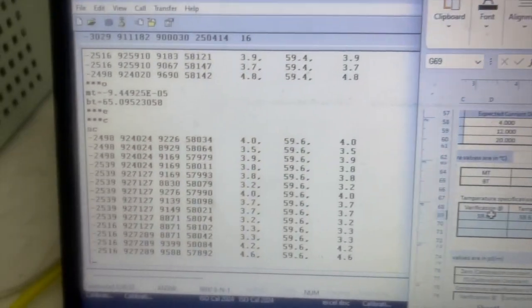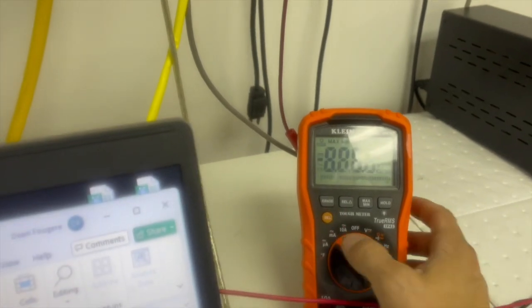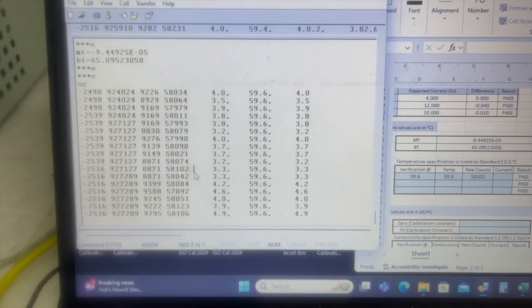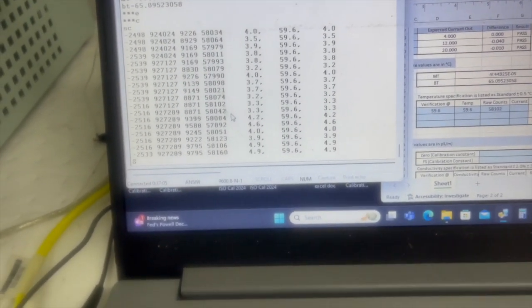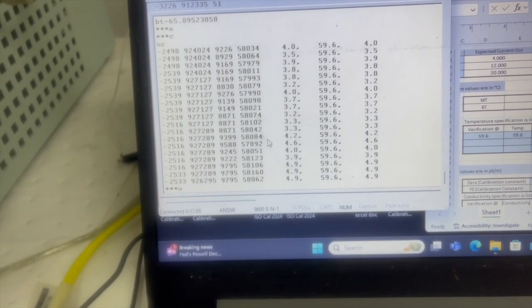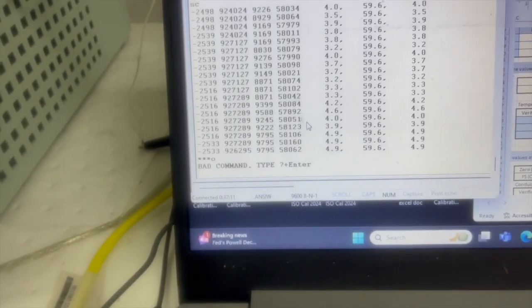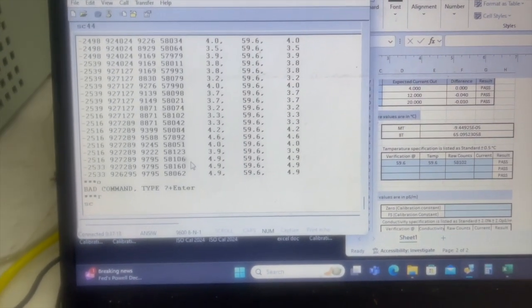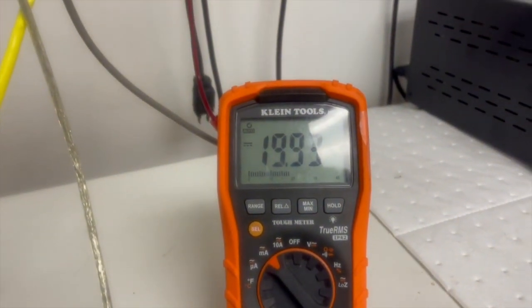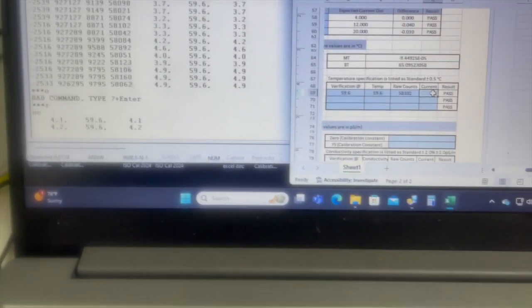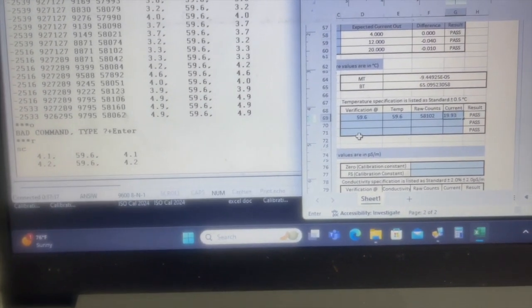And to get the current value, we need to turn on our current meter. Set it to milliamps. And we need to go over here, hit stop. Star O to get it back to open. Star R. And then hit SC to get it to start collecting data. And it should go at 59.6. It should be just under 20 mA, which it is. 19.93. And that is correct.